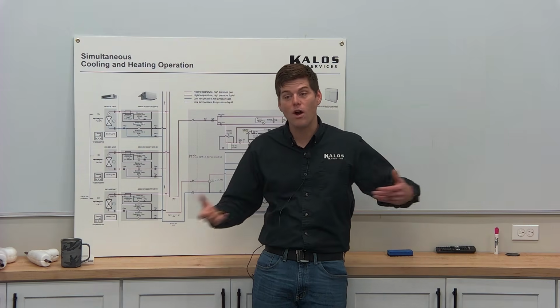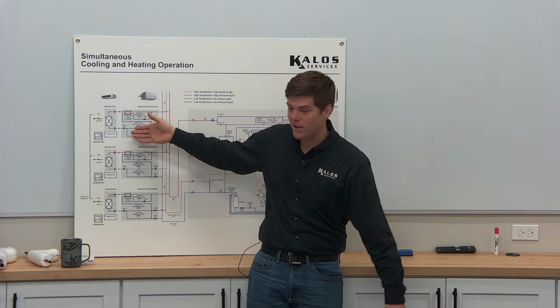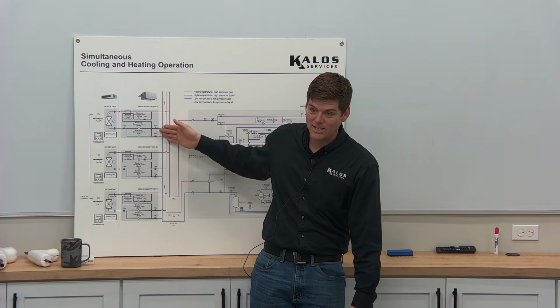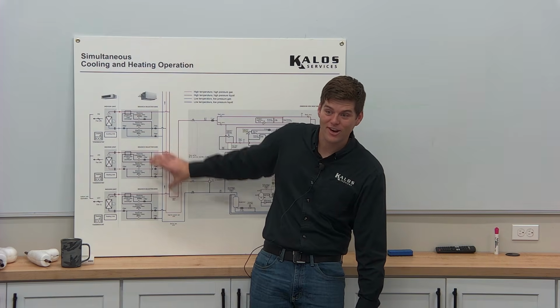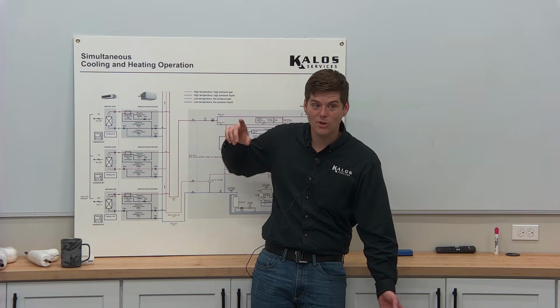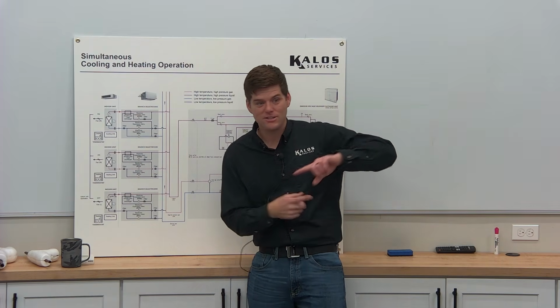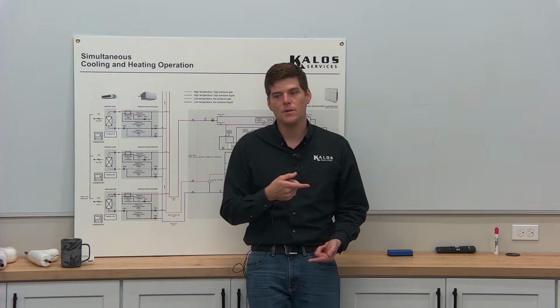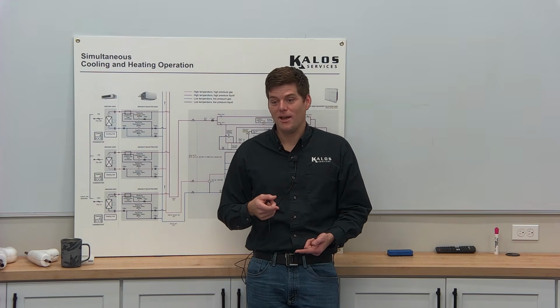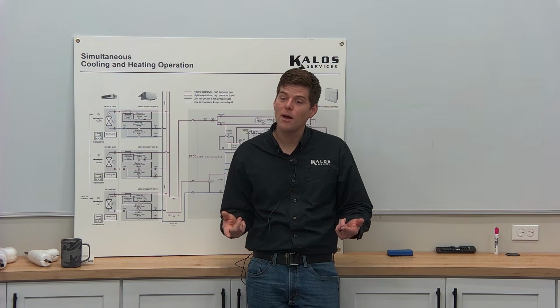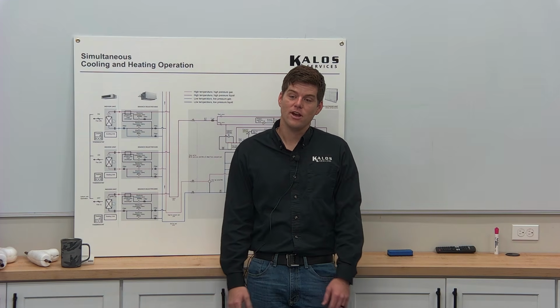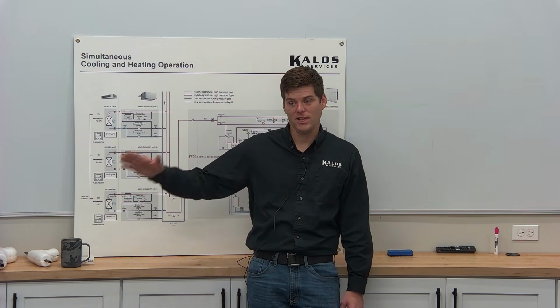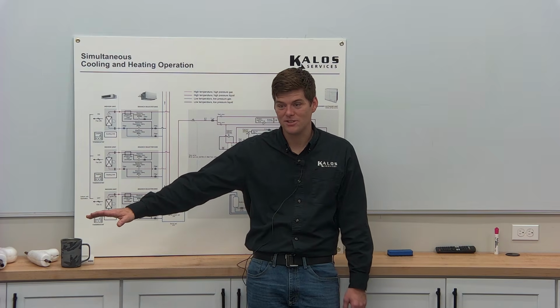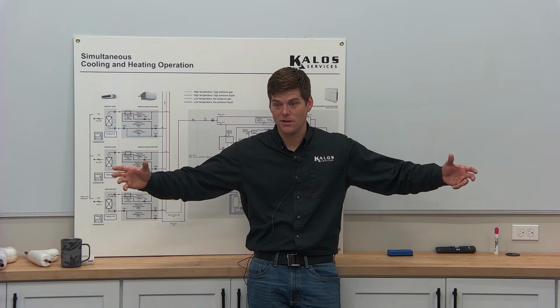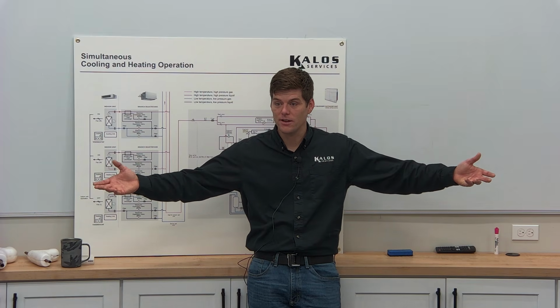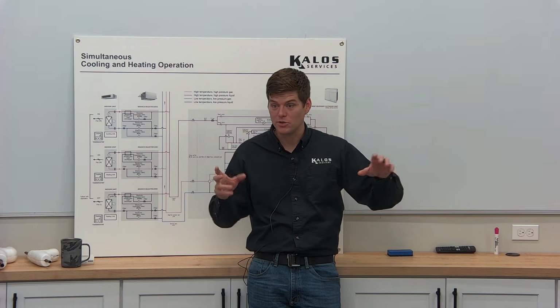Now, why do I say it's only one way? Because you can't take a vapor and then turn it back to hot gas. You would need a compressor somewhere in here, right? So it only processes one way for heat recovery. It doesn't go the opposite. It seems like more copper. What's that? More copper for this? Yeah. Well, it's more copper, but it's less work, less energy, right? So if I can run a system at like minimum speed and still deliver enough capacity for 4 rooms, by recirculating refrigerant, if you will, between indoor units.